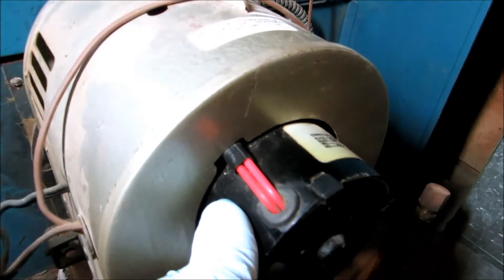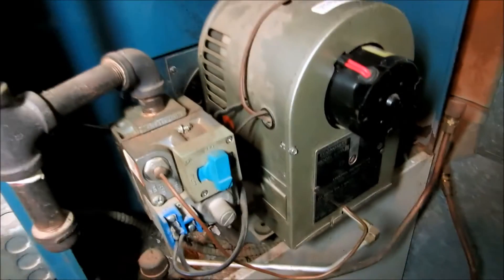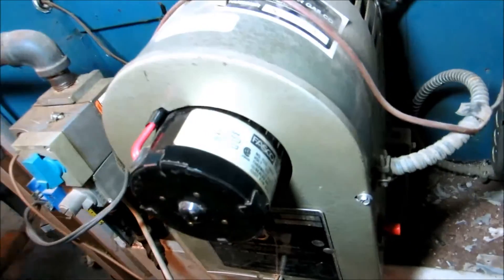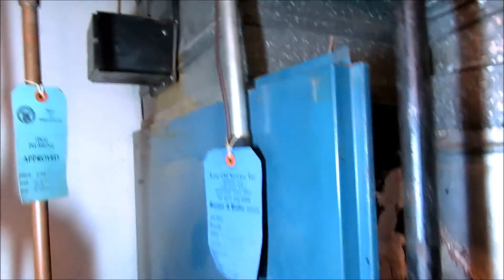I can see it vibrating. The conversion burner — your fan blade is out of whack. And like I said, it's not worth trying to get parts for that thing. This is from the gas company, and they no longer work on these. But we'll give them a price on changing the whole thing out.